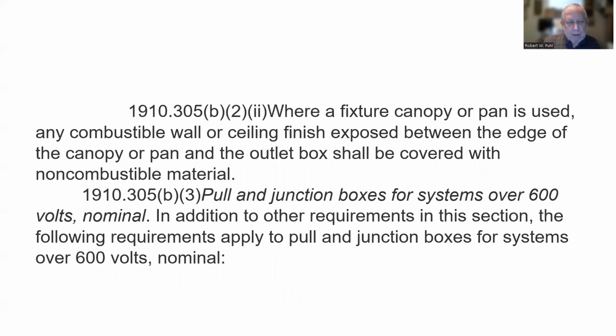If a fixture canopy or pan is used, any combustible wall or ceiling finish exposed between the edge of the canopy or pan and the outlet box shall be covered with non-combustible material.